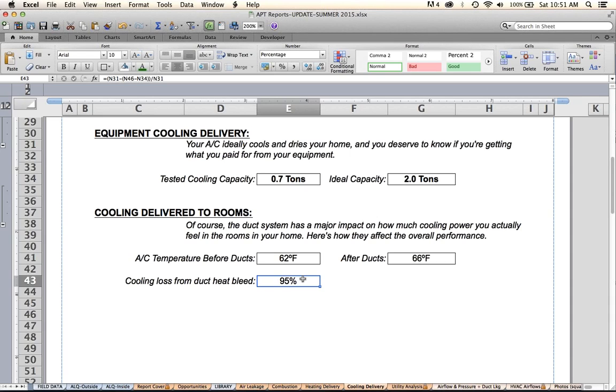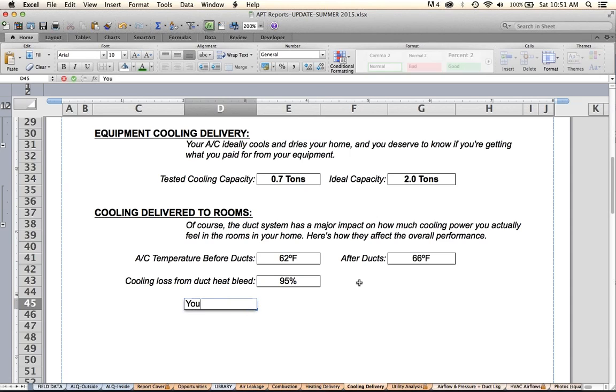But basically what we're going to do is say what the conductive loss and also probably the convective loss, but this is just cooling loss. This is not about duct leakage. It's not about duct insulation necessarily. It could be a number of things. Remember, heat flows in three different ways, so it's all of those. And it has nothing to do with airflow at all.